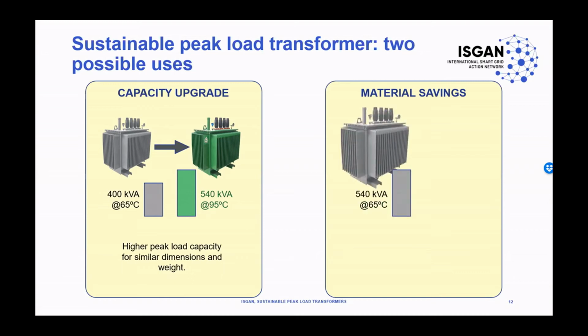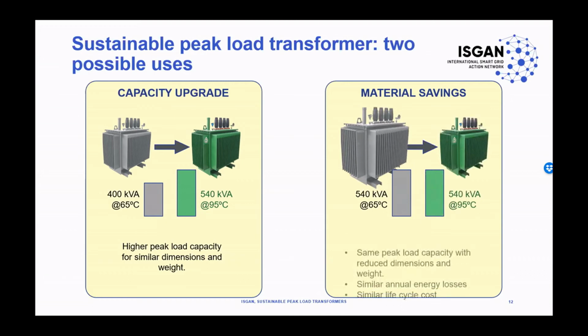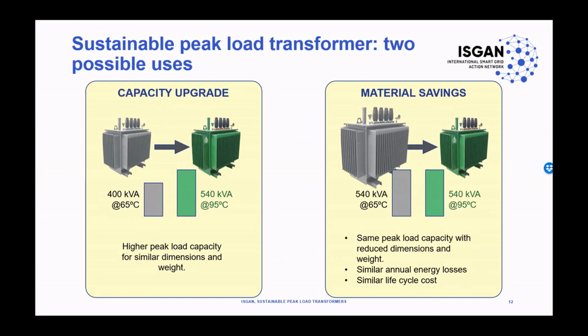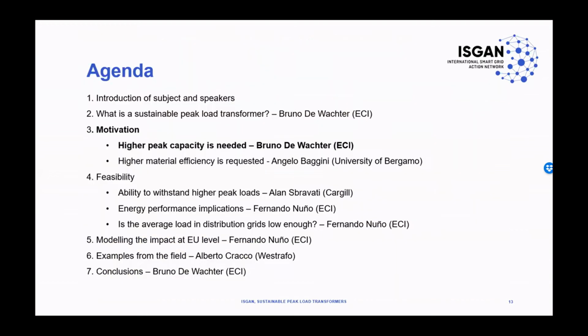The second interesting aspect of this concept is the material savings. Instead of having a 540 kVA transformer, which is substantially bigger than your 400 kVA one, you will have one of the same dimensions, so lower weight and lower material use than in the conventional one, and this for the same annual energy losses and a similar life cycle cost, and we will come to this later in the presentation. So this is basically the concept. We will now go into details of why these are two very interesting advantages.